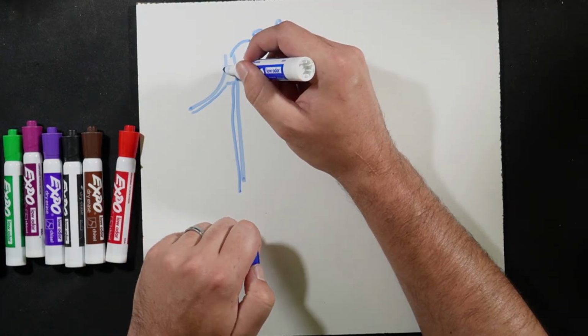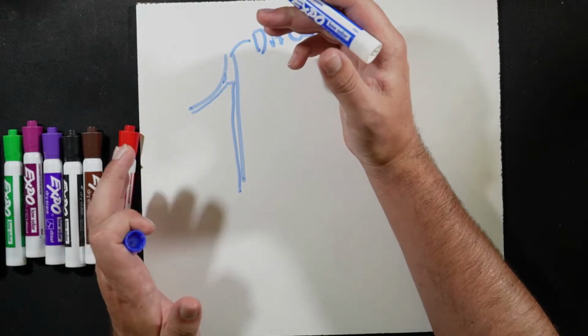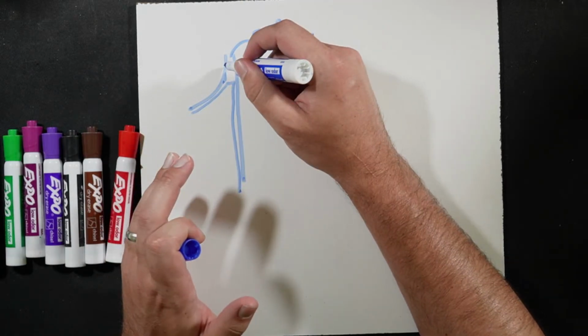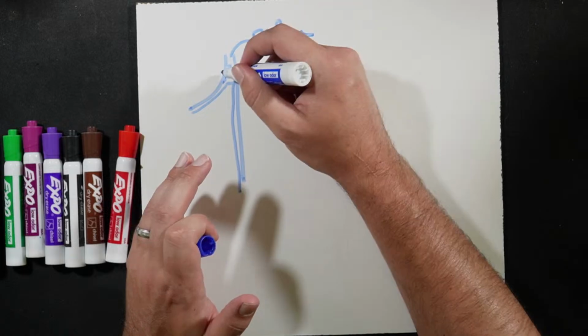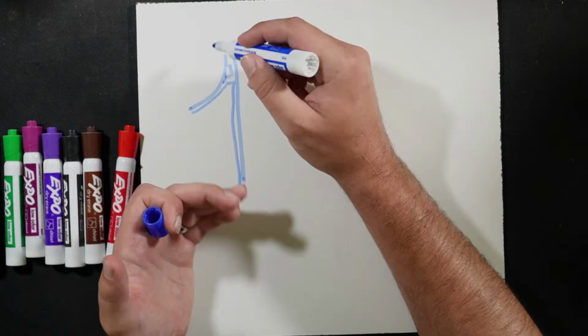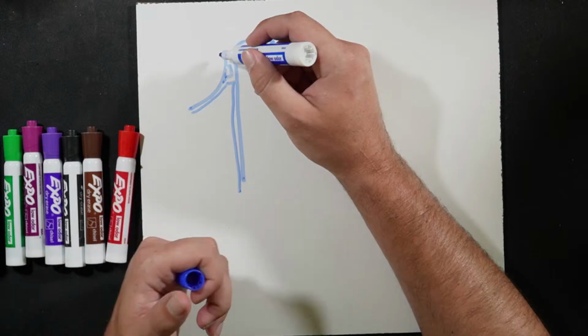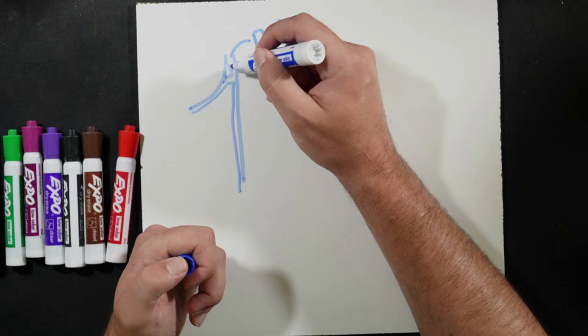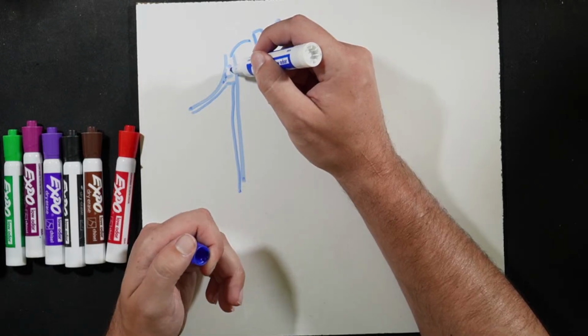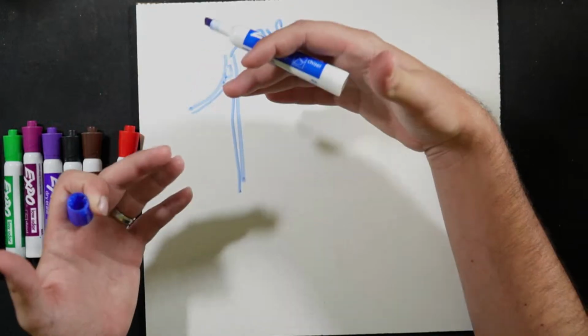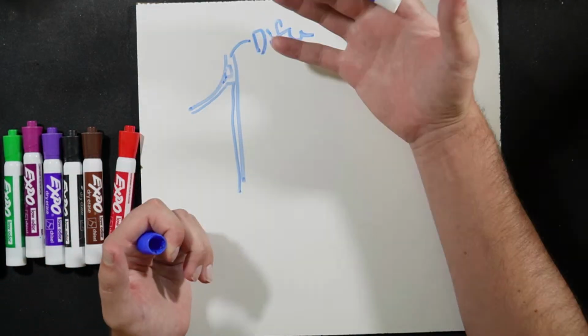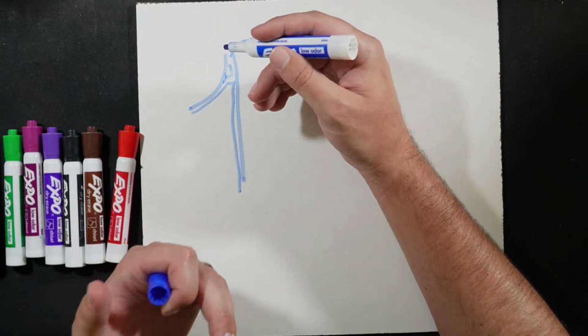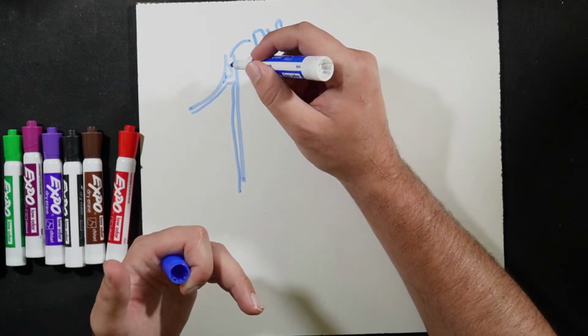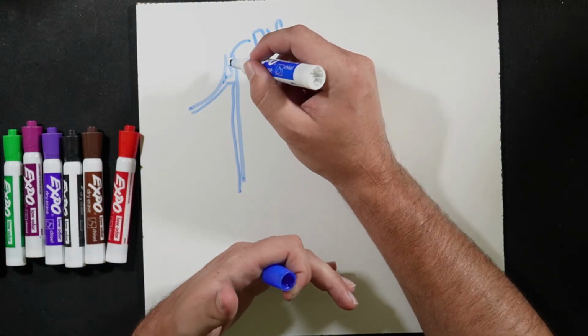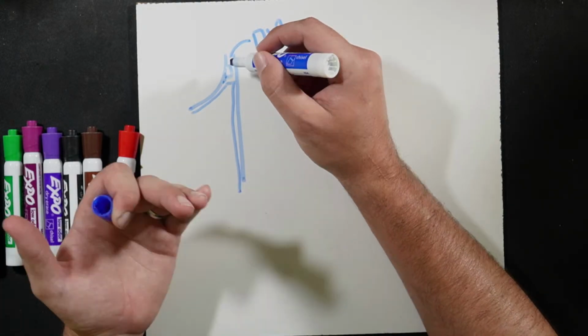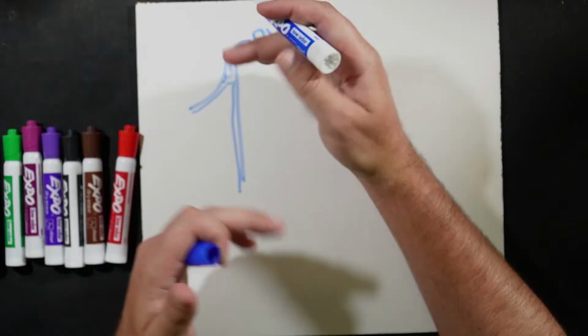We'll have a VGD in some of these increasingly more modern designs, where there's this ring that will slide in and out based off of an actuator, and it will change the dynamic of this diffuser gap. Now, the whole point of this diffuser is to start to convert the kinetic energy that the impeller puts on the refrigerant and convert that over into a static pressure, a potential energy. So we're converting that kinetic into potential, which is what we read with our gauge pressure. So this is the whole aerodynamic aspect of a centrifugal.